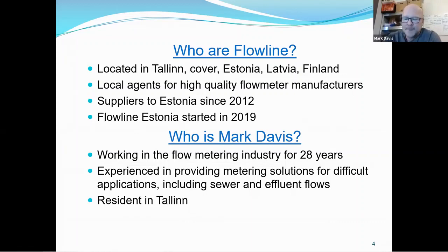And as Jorgen said, I've been involved in the flow metering industry for a long time. I now basically specialize in difficult applications, which usually involves effluent and sewer monitoring, a lot of retrospective metering. I would say about 90% of my metering applications are adding flow meters to a network or a system or a process where there wasn't a flow meter before. That's a very common application for us. And I'm located in Tallinn.